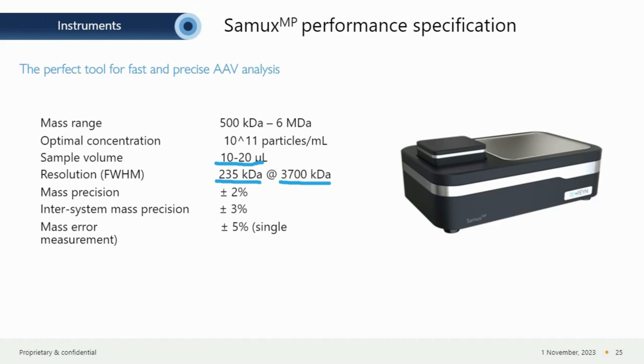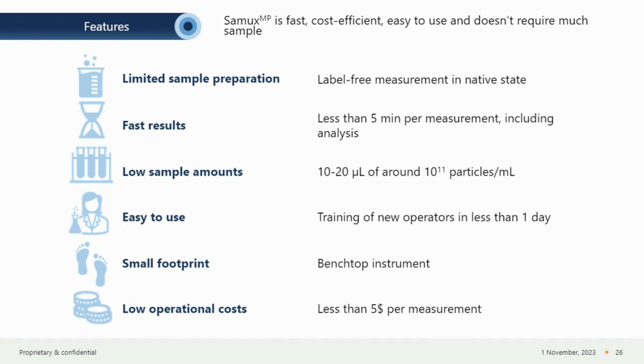To summarize: the SAMUX MP is a fast, cost-efficient, and easy-to-use system requiring little sample volume and sample preparation. It works at single molecule resolution with label-free measurement in the native state. Measurements including analysis take less than five minutes. Only 10 to 20 microliters and 10¹¹ particles per milliliter are required. It fits on a lab bench, and each measurement costs less than five US dollars. Less than one day of training is needed for new users to feel confident.